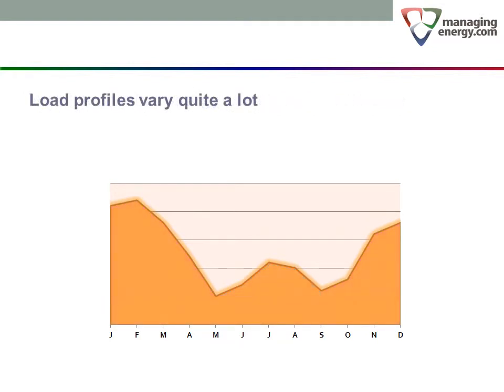The shape of the annual load profile depends on what equipment loads are connected. This meter serves some base load equipment in addition to heating and cooling systems. A building without cooling equipment would be heating sensitive but would show no summer peak at all. This profile is common for natural gas meters serving space heating and domestic hot water.